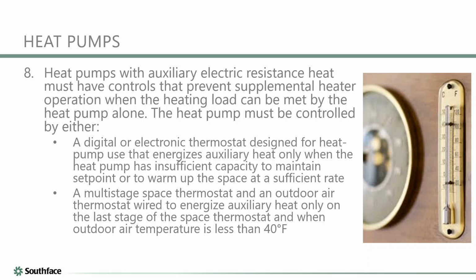Heat pumps. All right, this one is interesting. This one basically is saying that if you have a heat pump system, then the system has to work as much as it can, as low as it can. They're not allowing you to turn on strip heat or gas heat if the heat pump mode can suffice. Basically, because it's going to be more efficient using your heat pump mode rather than going over to your strip heat and or your gas auxiliary heat.